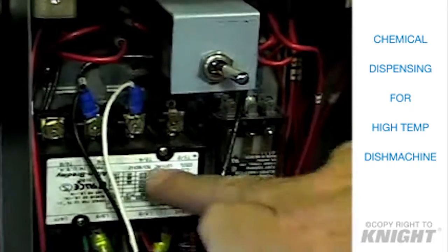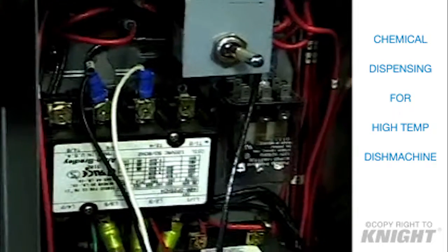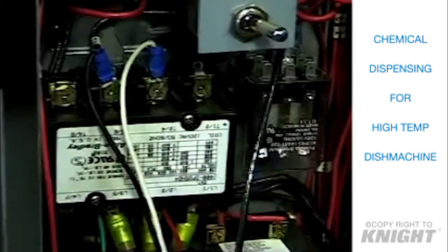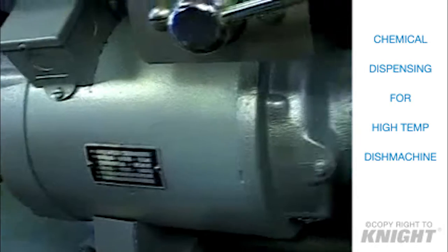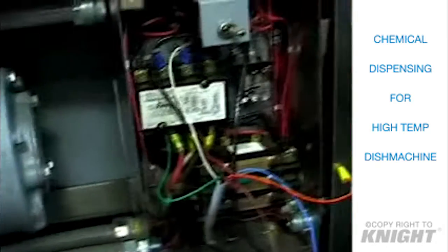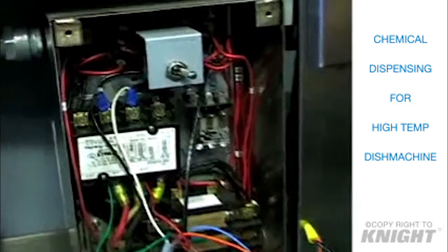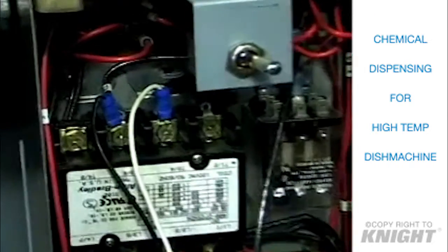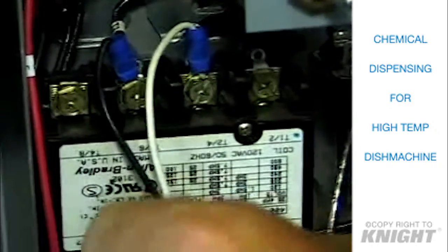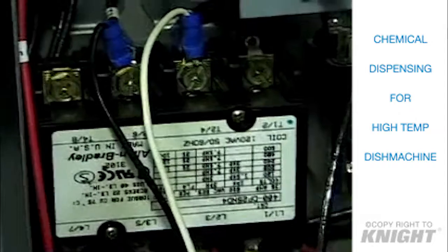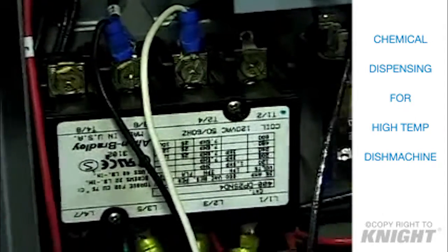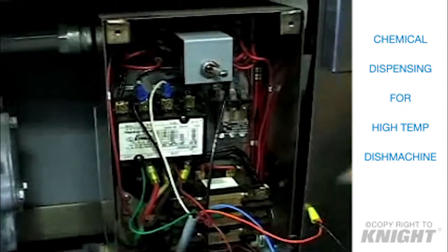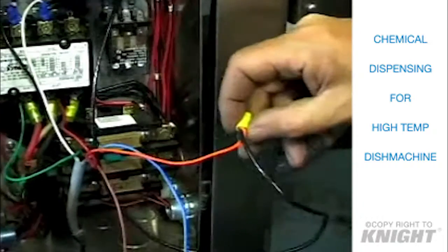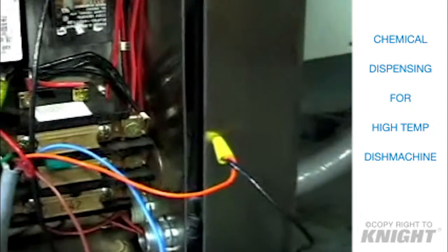So this magnetic contactor is just a great big switch to control this motor and the operation of this machine. So when this pulls in, this black and white wire, when we look inside the DigiSet, will be connected to the detergent signal. So every time I turn it on, this is going to activate it to sense what the probe is doing inside the unit. And every time the rinse paddle comes on, my signal is going to go up on the brown and orange wire and make my rinse pump run.